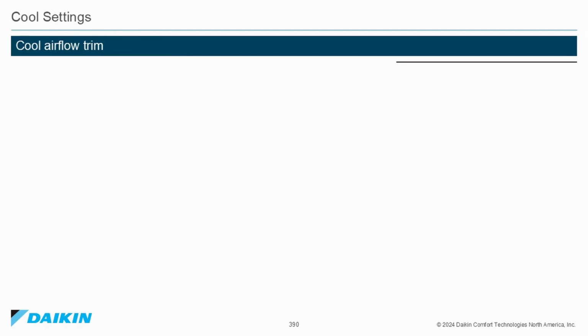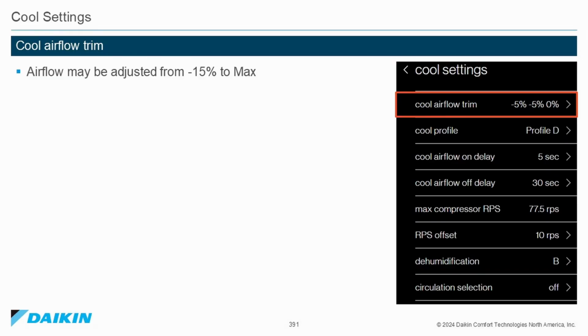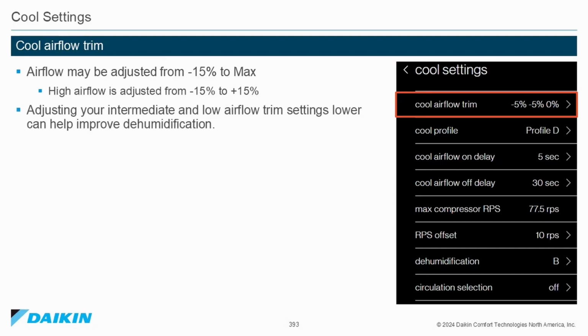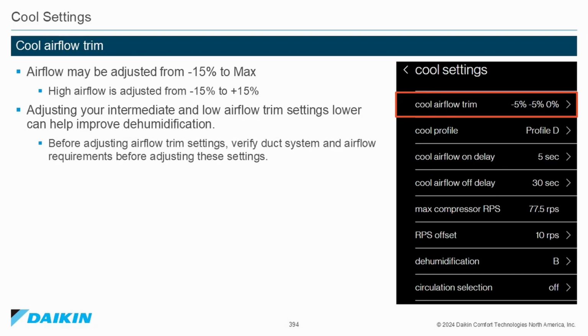Cool settings. Cool airflow trim. Airflow may be adjusted from -15% to maximum. High airflow is adjusted from -15% to +15%. Adjusting your intermediate and low airflow trim settings lower can help improve dehumidification. Before adjusting airflow trim settings, verify the duct system and airflow requirements are met. Refer to the I/O manual for restricted airflow combinations.